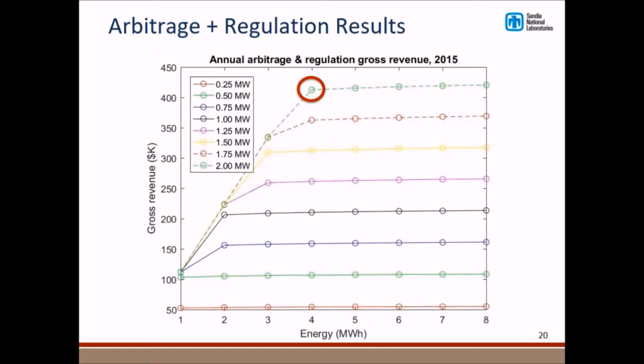This chart shows more of the data—it's the full sweep for 2015. The red circle shows the size of the system, which is 2 megawatt, 4 megawatt-hour. You'll notice there's a knee in the curve, and that knee is just from frequency regulation. You want your capacity to be roughly twice your power rating, so you can sit at 50% state of charge and then bid the full amount into the frequency regulation market.